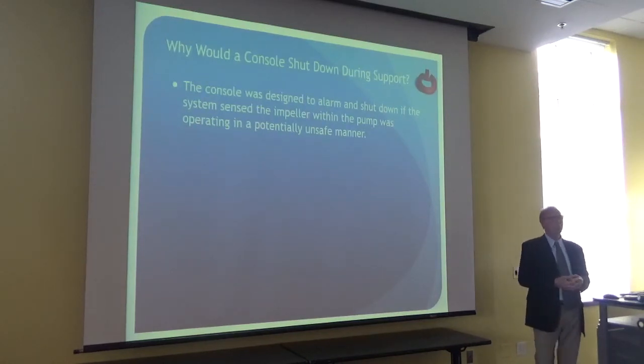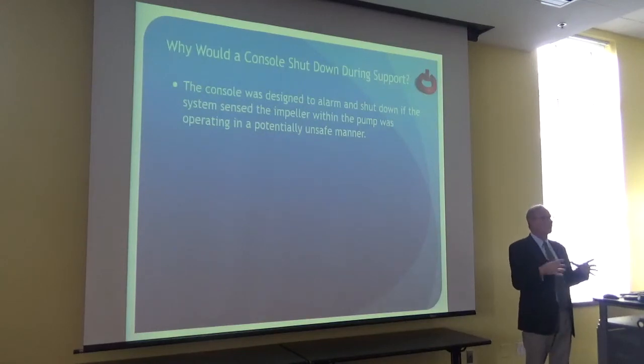and may be operating in a potentially unsafe manner. So what do I mean by that? Since we got the impeller and we are electromagnetically controlling its orbit, its central position, and causing it to rotate, if that orbit widened and it touched the side, it could cause a scratch or a problem, leading to thrombus, leading to potential thromboembolism and stroke.